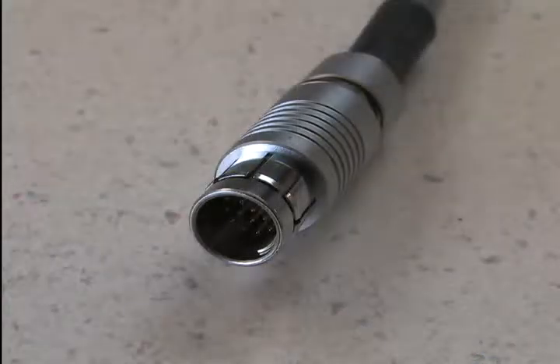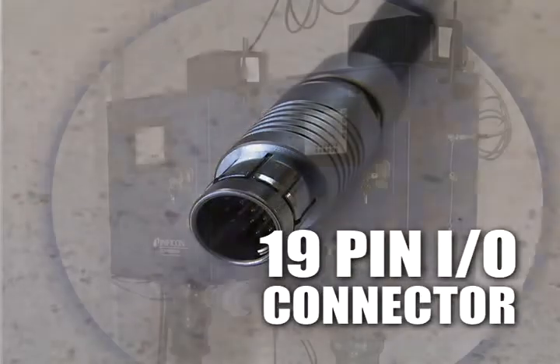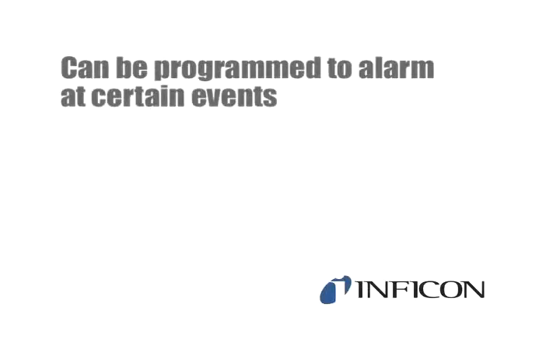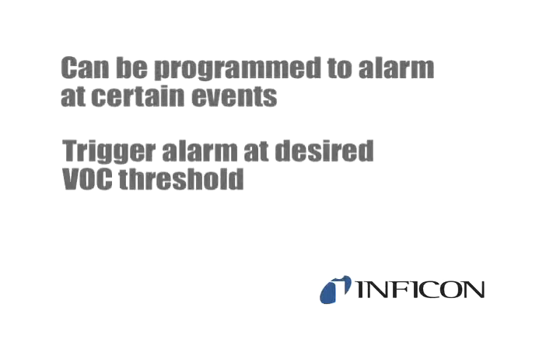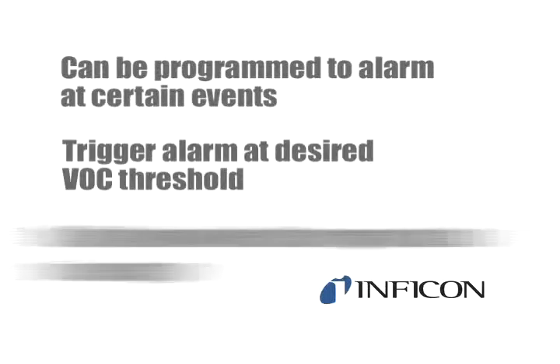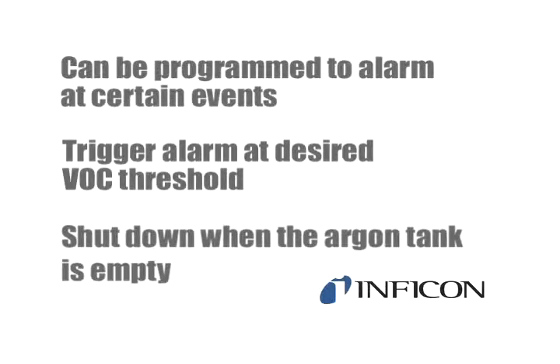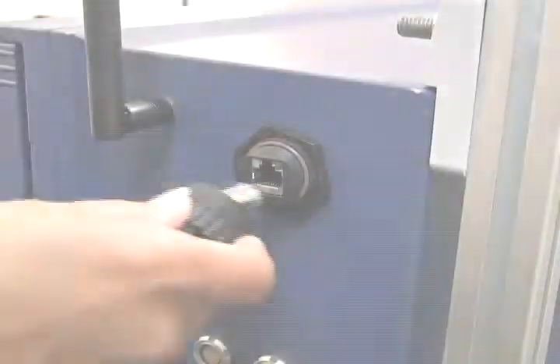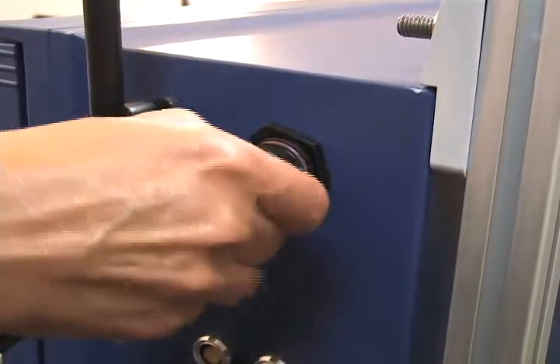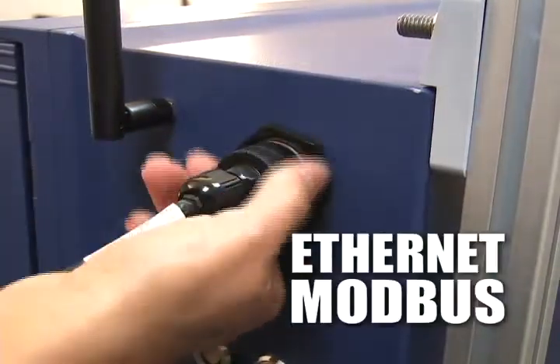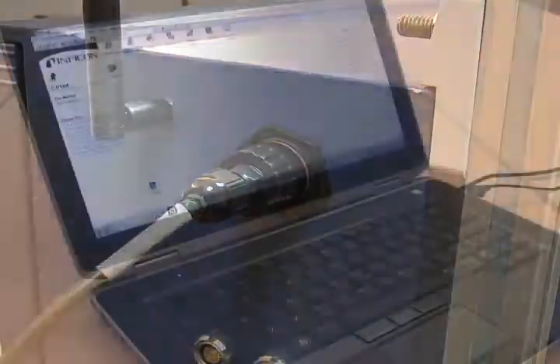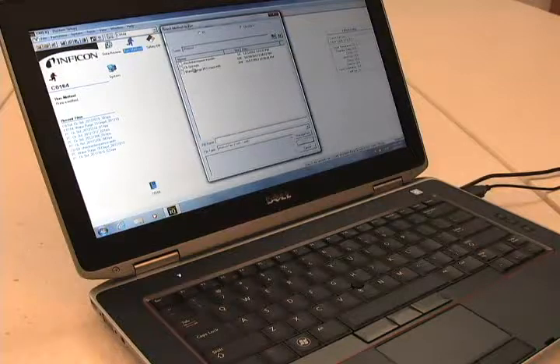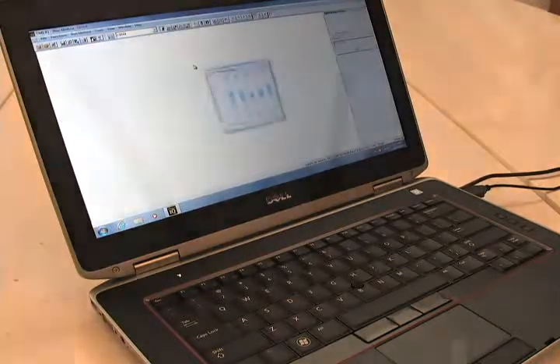The instrument can be integrated into a SCADA system using a 19-pin I/O connector. With 6 outputs available, the CMS5000 can be programmed to alarm during certain events, such as triggering an alarm at a desired VOC threshold or triggering the instrument to shut down when the argon tank is empty. The CMS5000 can also be integrated using the Ethernet cable or Modbus protocol. Data can be automatically uploaded to an FTP server and retrieved over the Internet.